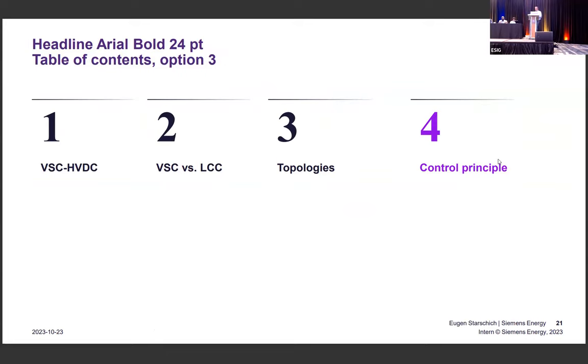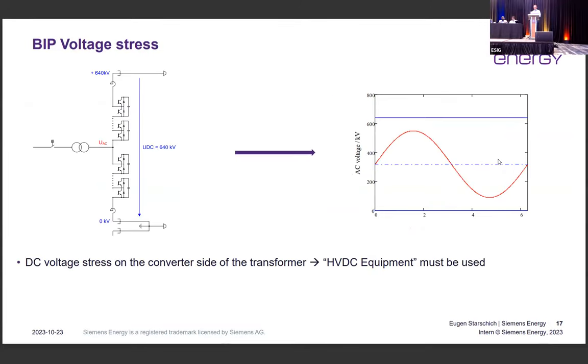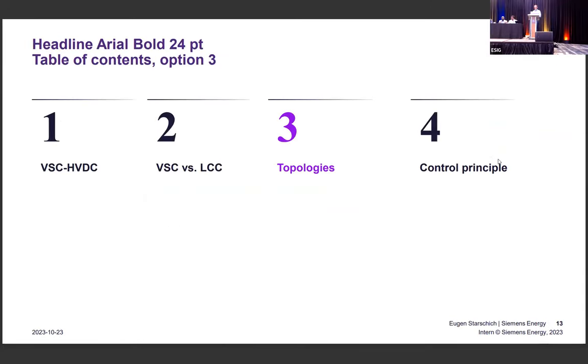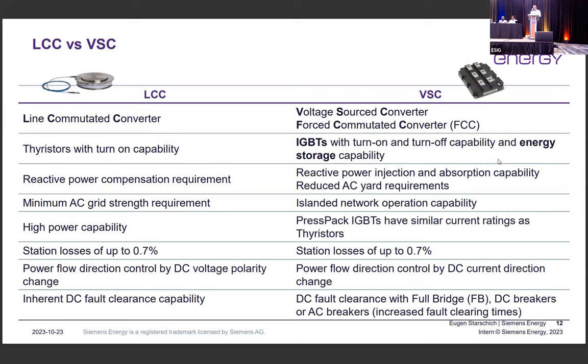As mentioned before, it would be pretty handy to have a DC breaker for the DC fault clearance in a multi-terminal system. There are many suppliers who are offering DC breakers. They say they have different DC breaker technologies being developed. So far in the Western region, outside of China, there are no DC breakers in operation right now.